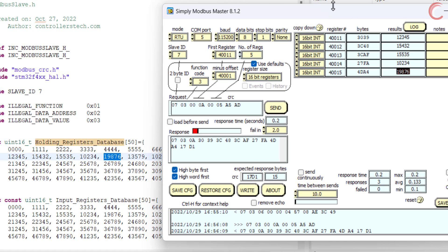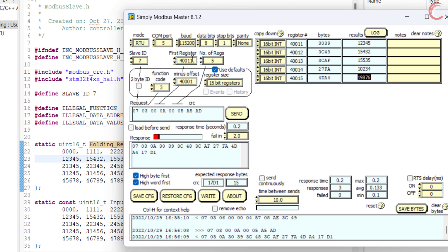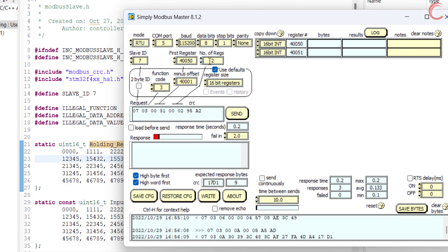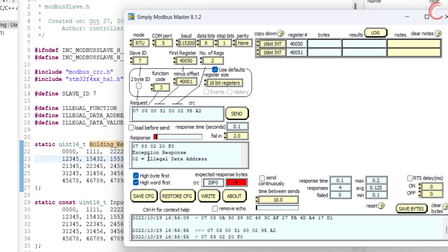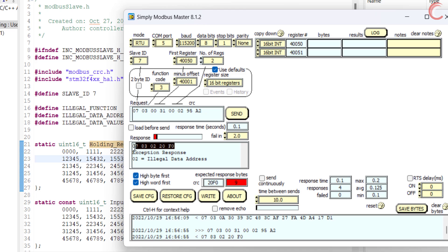Let's see the exceptions now. As I have already mentioned, there are a total of 50 registers defined in the database. If the master wants to read two registers starting from 40050, the register 40050 is present in the database but 4000051 is not. Therefore the slave will return an exception saying the address is illegal. Here you can see the master was expecting nine bytes, but it only received five. The exception response will always have five bytes: one for the slave ID, one for the function code, one for the exception code, and two for the CRC.